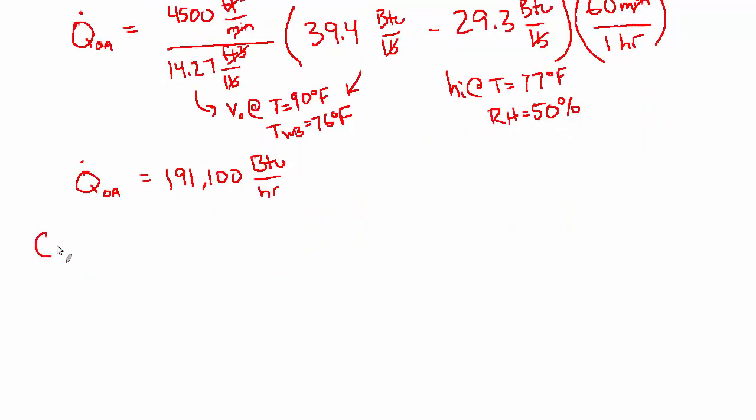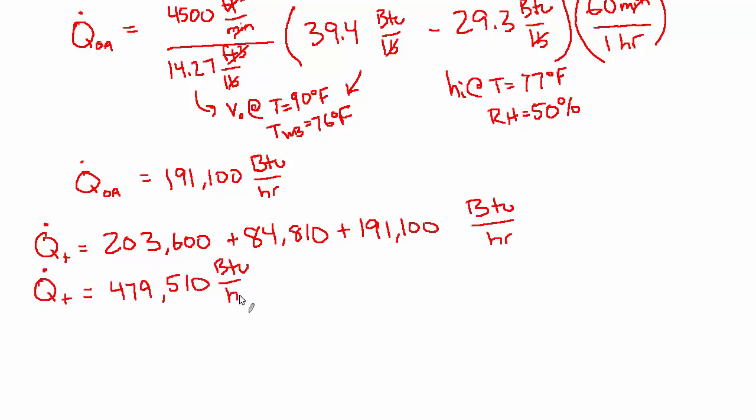Let's add them all together. Q total is the sensible 203,600 plus the latent 84,810 plus this outside air piece, 191,100. And all of those have units of BTUs per hour. So the total is 479,000 BTUs per hour.